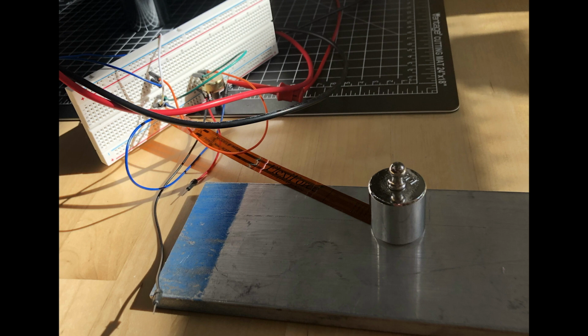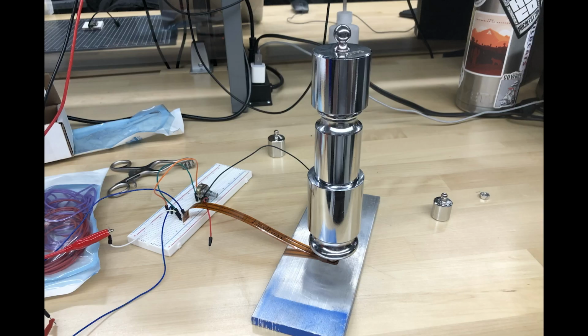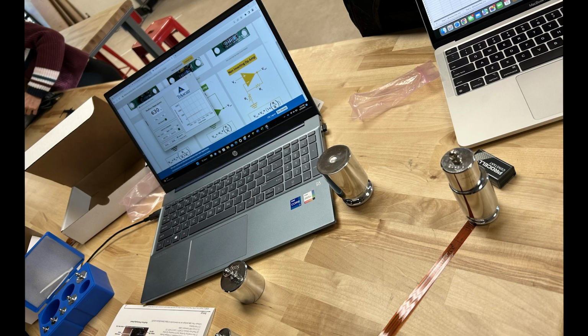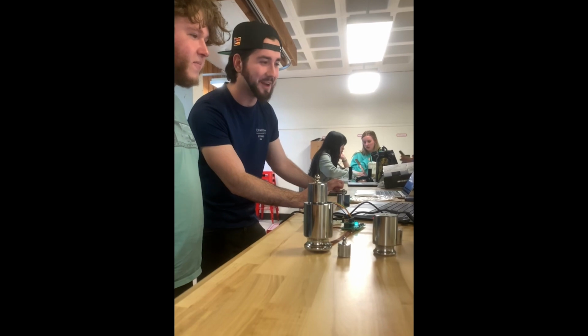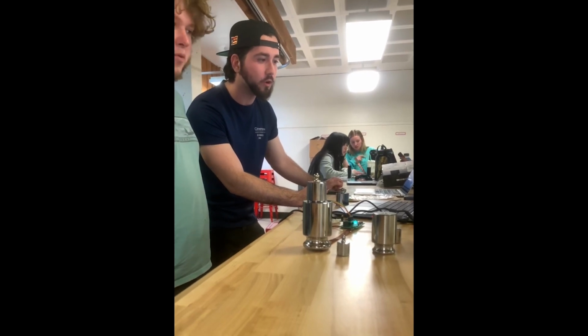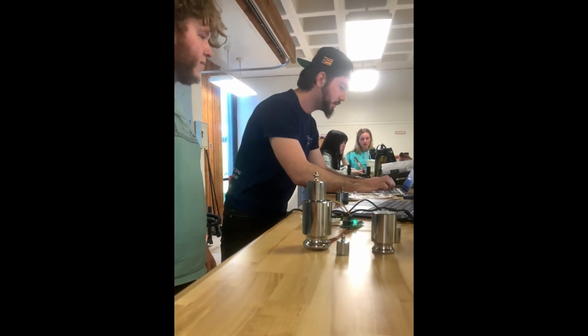Prior to testing our system prototype for precision and accuracy, we calibrated it according to the range of forces that we wish to detect, from 1.96 to 19.61 newtons. By nature of being force measuring sensors, the Flexiforce A201 sensors we incorporate in our system are understood to satisfy the ASTM E74 standard practices for calibration and verification for force measuring instruments, another of our verification requirements.